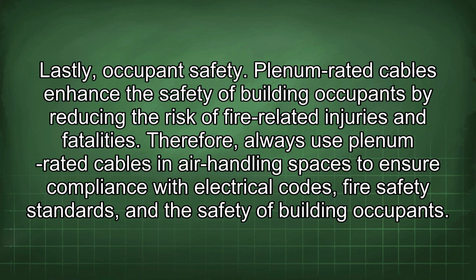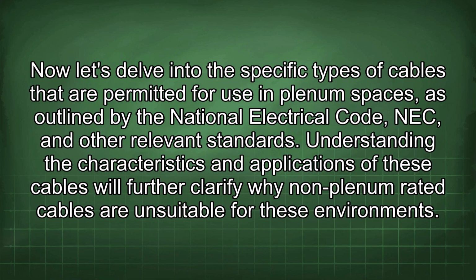Therefore, always use plenum-rated cables in air handling spaces to ensure compliance with electrical codes, fire safety standards, and the safety of building occupants. Now let's delve into the specific types of cables that are permitted for use in plenum spaces as outlined by the National Electrical Code, NEC, and other relevant standards. Understanding the characteristics and applications of these cables will further clarify why non-plenum rated cables are unsuitable for these environments.